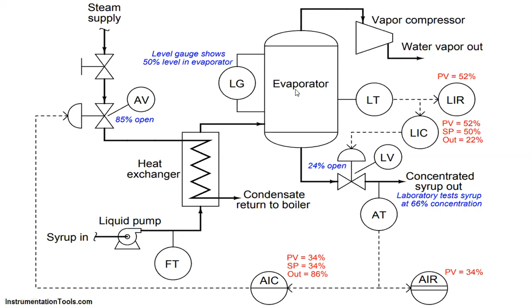We have a level gauge, because the evaporator level is very important. That's the reason why we have a level transmitter, level indicating controller, and level indicating recorder. This level indicating controller is interlocked to the control valve through which the concentrated syrup is going out, right? If you allow more, the level will come down. If you allow less, the level will be maintained here. That's exactly the control that is adopted here.